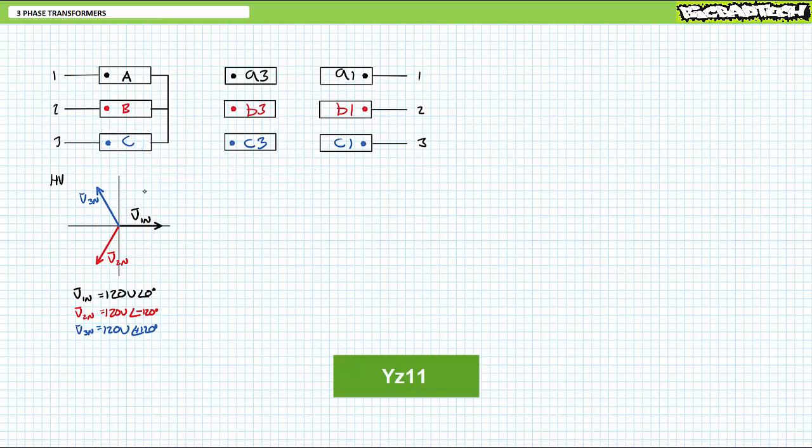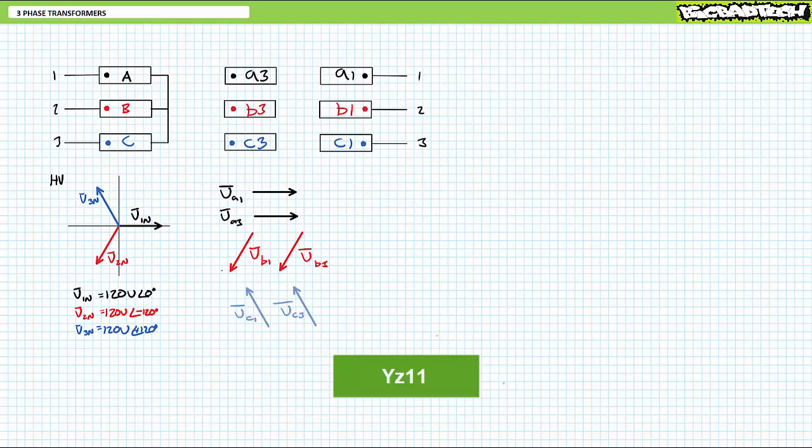For the sake of argument, let's say both the low voltage windings have one-to-one turns ratio with a high voltage input such that if we're making use of light industrial 60 hertz three-phase AC characterized by 120 volts line to neutral, 208 volts line to line. Both A1 and A3 would be 120 volts at an angle of zero degrees. Both B1 and B3 would be 120 volts at an angle of negative 120 degrees. And finally, both C1 and C3 would be 120 volts at an angle of 120 degrees.